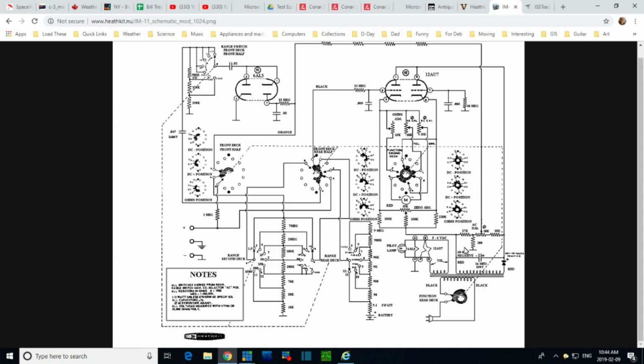They're using a very unusual symbol here. Look over here for a minute. This is the typical earth symbol. What's that? That looks like the chassis symbol with the little hash marks missing. It's all over the place, so I'm pretty sure that's what that means, tied to chassis. And this is actually tied to what? What would this be connected to that would be so different? It's only a 2-pronged plug. Earth to what? Or maybe you're supposed to put an earth on that, an earth connection. And this, well, I don't know. I was going to say maybe this is just showing it's connected to the case. But no, this is connected to the case. I don't know. I'm a little bit confused about that. Anywhere else you see a ground terminal? No, just right here. Okay, so I'm not sure what's going on with that.